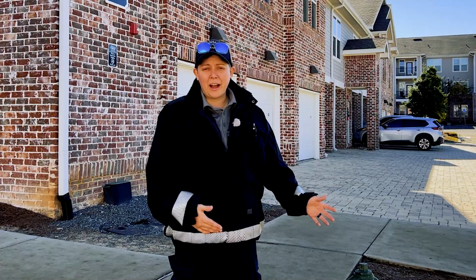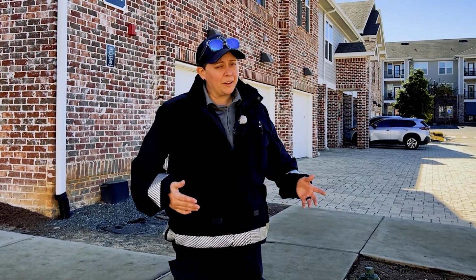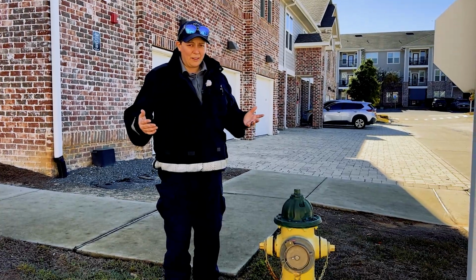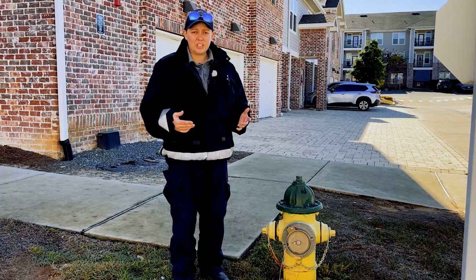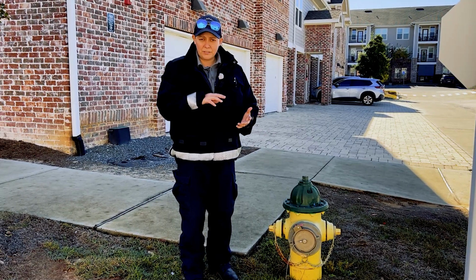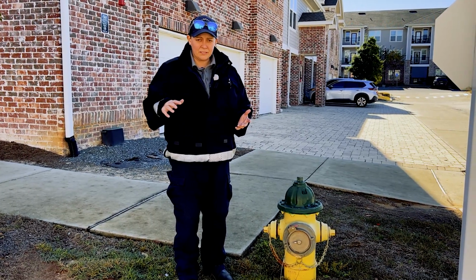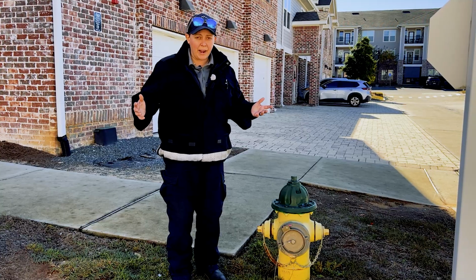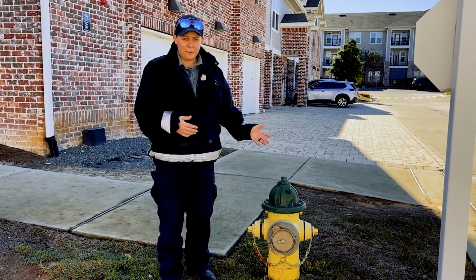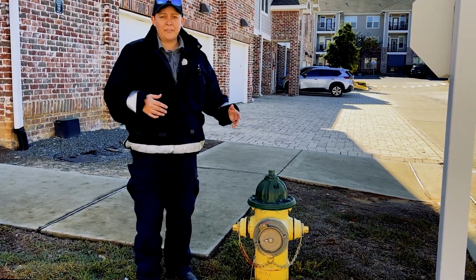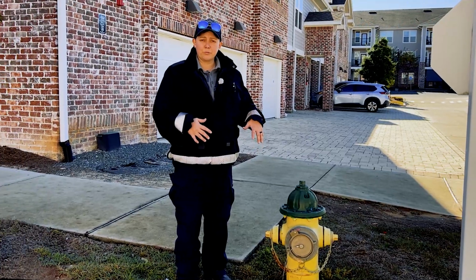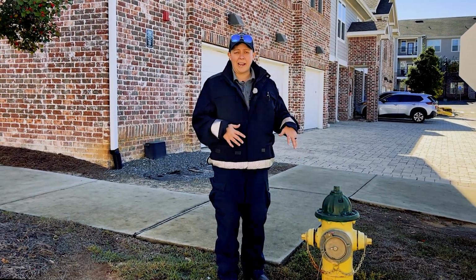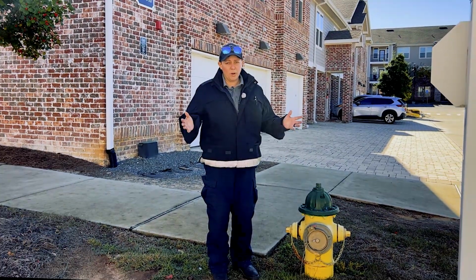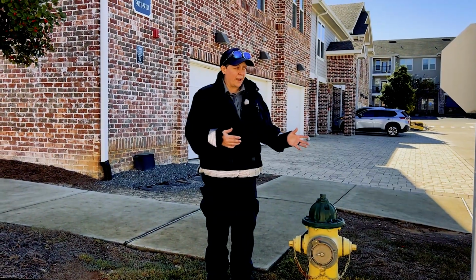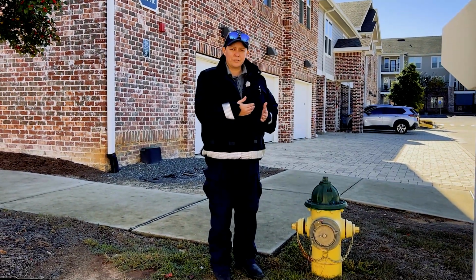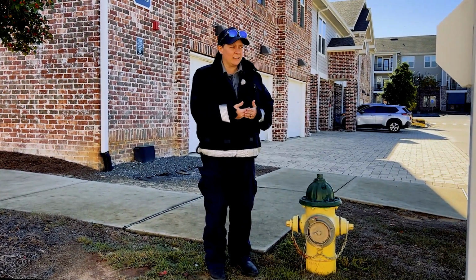Right now I'm in front of one of the hydrants. This is a private hydrant. How do you define that? You Google Leon County fire hydrants and the GIS report will populate up. You can type in your address at your business or even your home and figure out where your hydrants are. With this business, I went to the GIS report and found that they own this hydrant, so they're responsible for pressure testing it annually. Annual basis means once a year. This is private, so they have to make sure the water and pressure is there in case we have a fire.